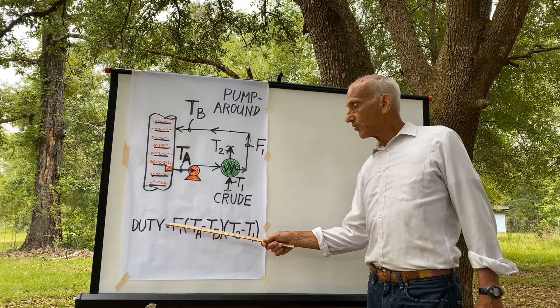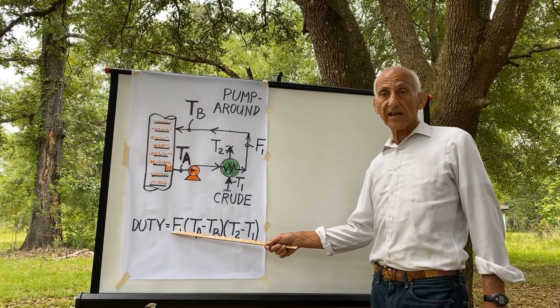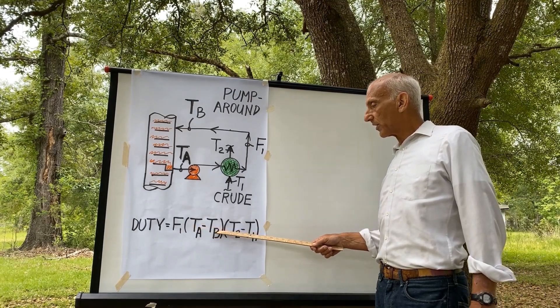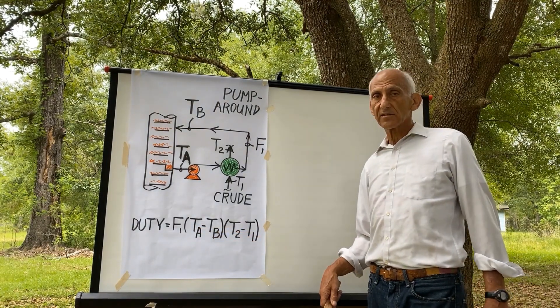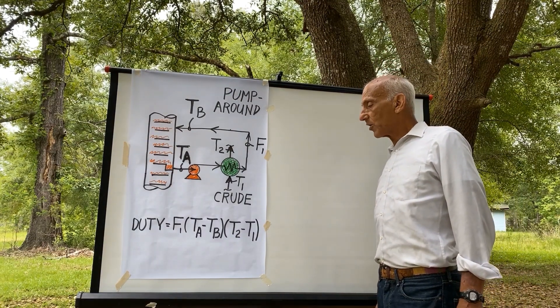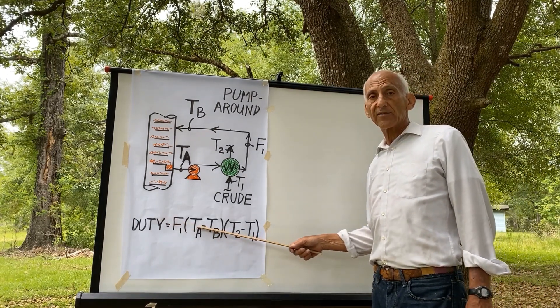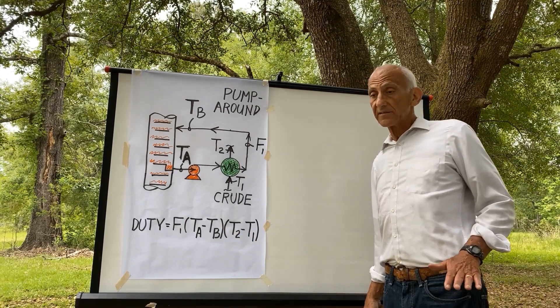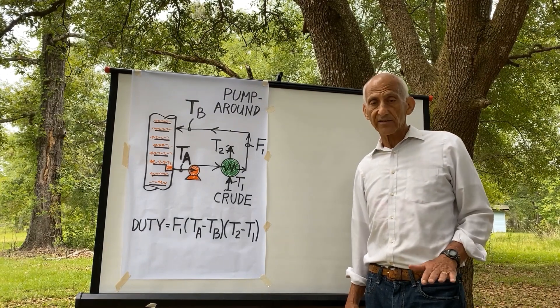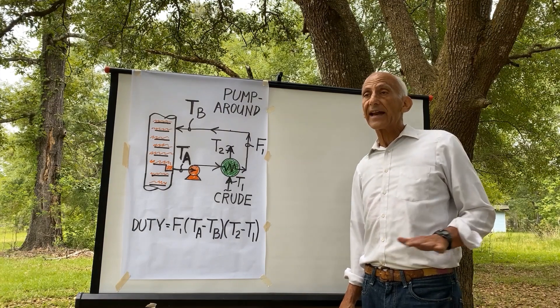So as one increases the pump around flow rate F1, F1 will go up, but this temperature difference is definitely going to go down. Very often — perhaps half the time — increasing the pump around circulation rate will cause the pump around duty to go down and not up as you desire.